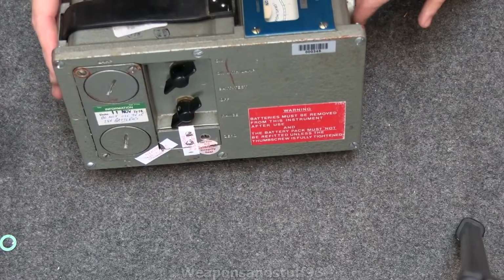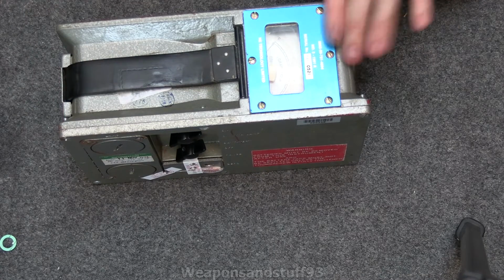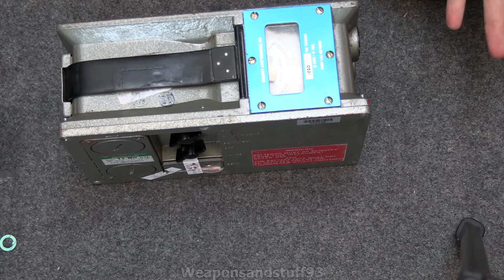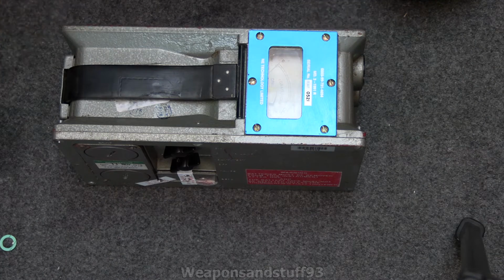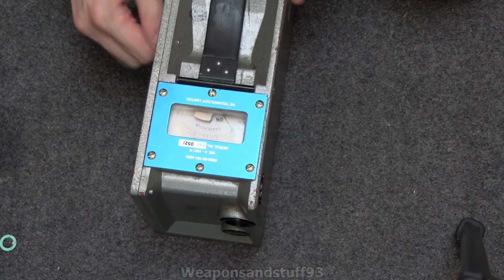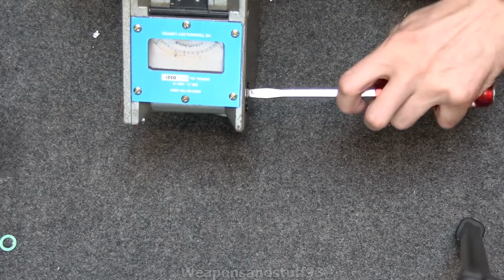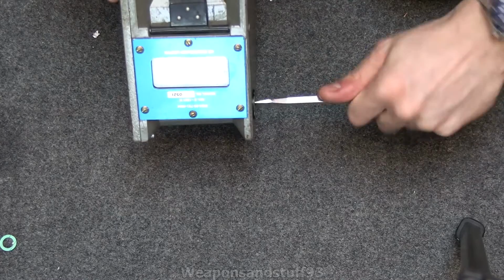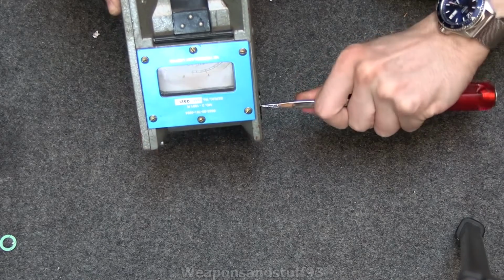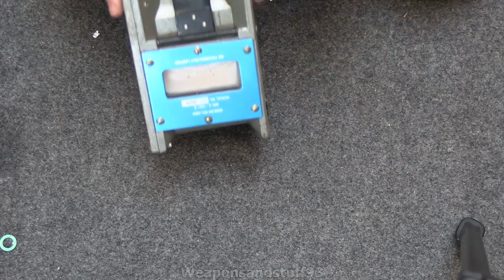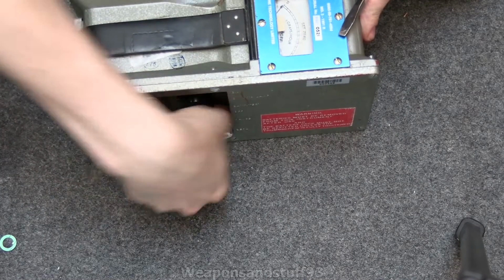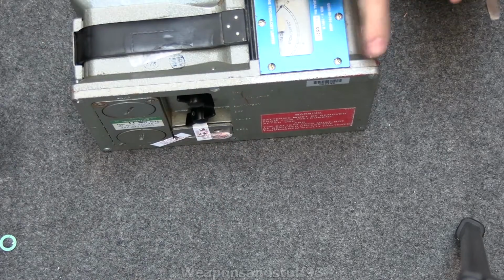So that's basically the complete basic guide to setting up an old British MD3 meter. As said, you can pretty much get it down to stick new batteries in, replace the silica gel, you're good to go. As said, sometimes the lamps can be a bit fiddly, even if your bulb isn't blown. Sometimes you need to unscrew and screw them in to let the lamp function work. But yeah, even looking at this one, this lamp is jolting on and off. Some of these are really strange where when the lamp is fully done up, it's actually not as bright as before. But essentially all the lamp function does is power the little bit the lamp connects to there.